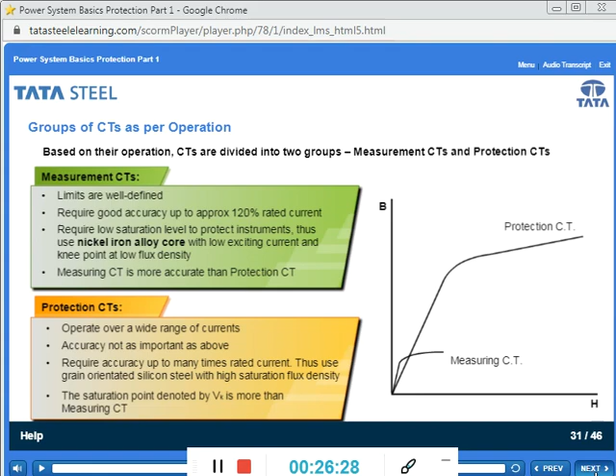As for all equipment, CTs also follow a naming convention. It goes something like this: 30, 5P, 10. Now what does that mean? Well, 30 is the rated VA or burden, 5P is the class, and 10 is the accuracy limit factor or ALF. Click on each tab to learn more.